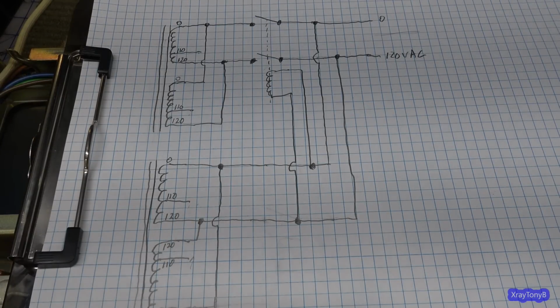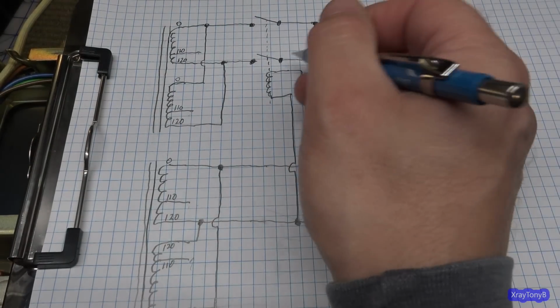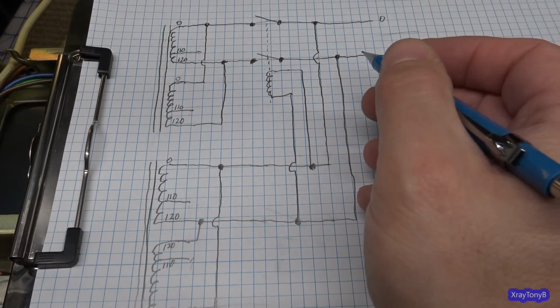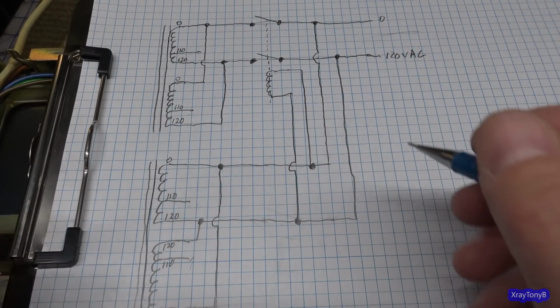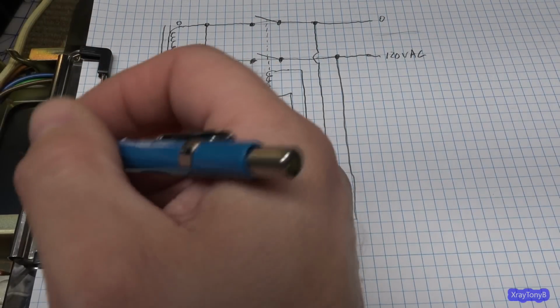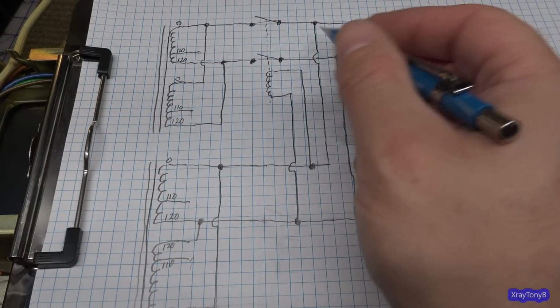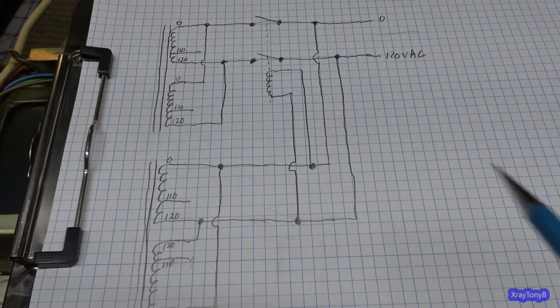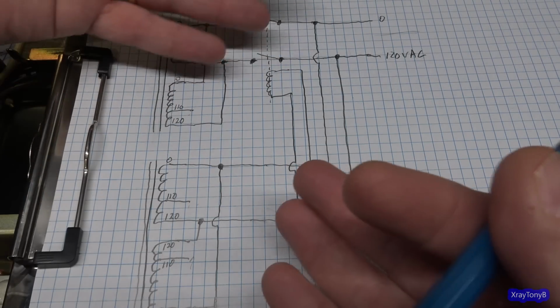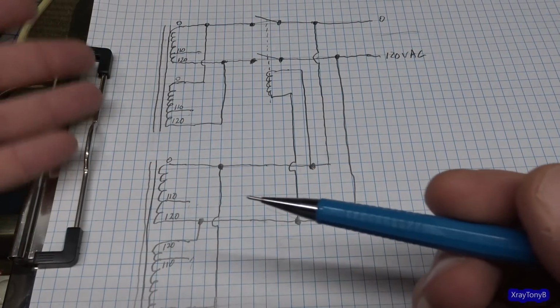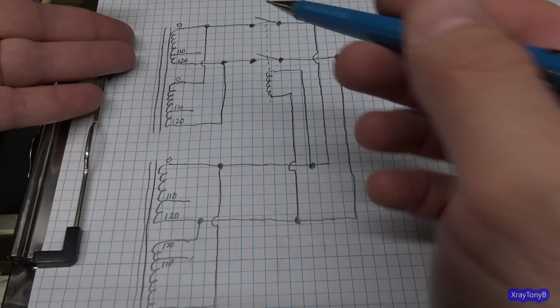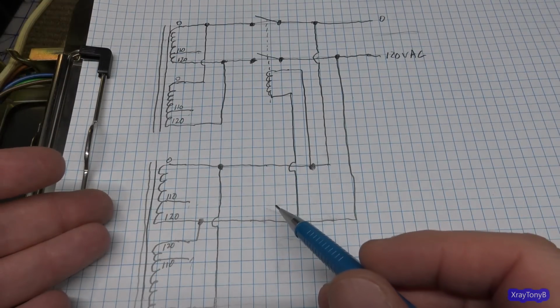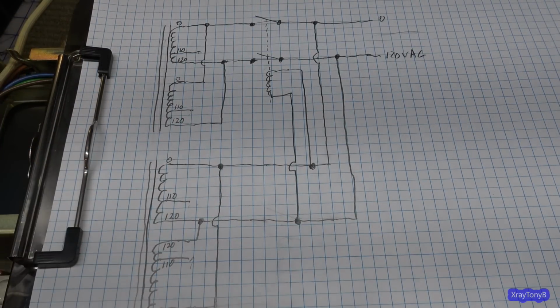Weird. Wouldn't it be easier to just direct wire these like this and then have one of those little soft start modules I made, that works off the capacitor charging level, on each one? Each one can soft start individually. It doesn't matter, one has nothing to do with the other, and when this cap bank gets up to a certain amount, the relay will bypass the soft start resistor, and the same goes for here. So that's what I'm going to do. I'm going to wire it for that and get rid of all this.